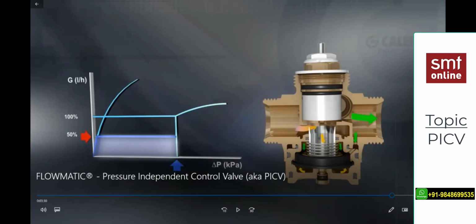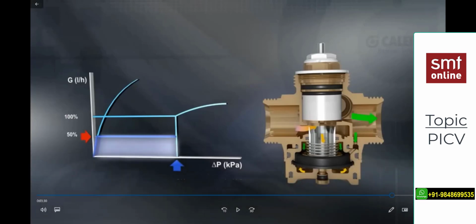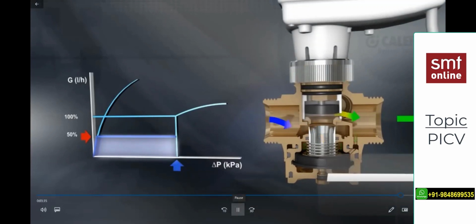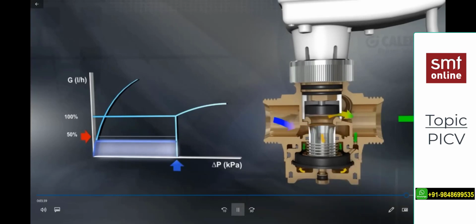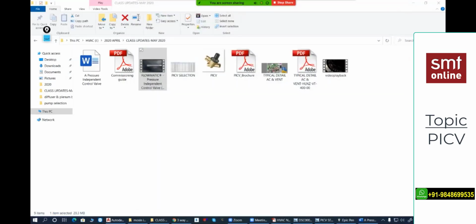In the case of a normal two-way or three-way valve, the excess pressure is borne by the valve itself. But in this one, the excess pressure is utilized to push the spring. So the life is also good in this PICV compared with the two-way and three-way. Getting my point? So, one time only we balance, and it will automatically monitor the flow as per the requirement.